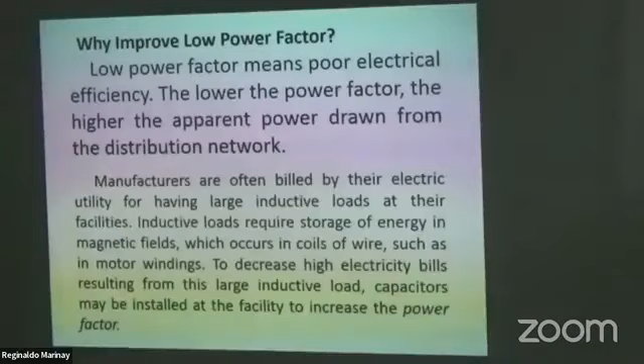This apparent power, that is your KVA demand from the utility, from the source. Isn't it that when we calculate the electrical design, we get the volt-ampere of your building? If you want to calculate the size of your transformer, you have to calculate all the loads first, right? That will be the basis for sizing your transformer and your generator. It's very important, and you'll see that in the load schedules. Attend the training, we have training about electrical design.